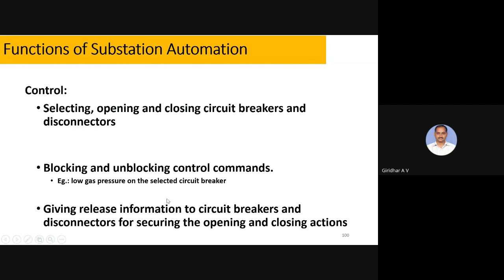So these are the various functions of substation aspects. In automation control, we are selecting and opening, closing circuit breakers and disconnectors; blocking and unblocking will also be used here. Suppose in a particular circuit breaker there is low gas pressure, and we should not give initiation of that control. So we have to block it so that the necessary action will be taken. Those things will be properly done with blocking and unblocking commands before going to action, passing into that state. In that way, the information to the circuit breakers will be passed in a very secure way, for opening and closing actions.